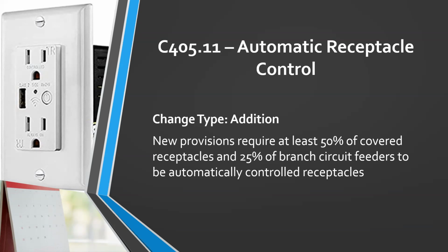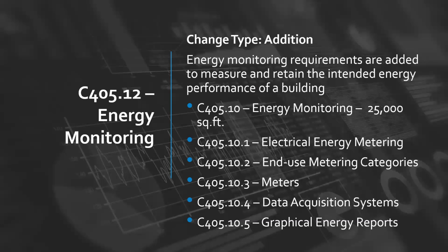So that's something that people are having confusion with on how to set those up, which rooms are actually required to have that. Most of the time, it's in dorms, it may be even in the dorms themselves, but the majority of the time, if it's in an office building, it's going to be in the common areas where you have seating for the general public, or you have common areas for offices or meeting rooms, not really in the offices themselves. It will be in a common area. So those are requirements that are listed in those books. I didn't put everything in there. That was just kind of the addition that's going on. But as you can see, a lot of it's more and more and more controls.